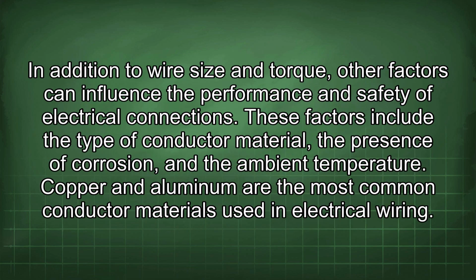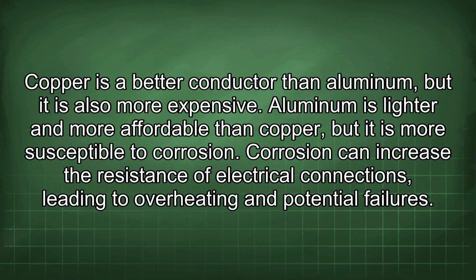In addition to wire size and torque, other factors can influence the performance and safety of electrical connections. These factors include the type of conductor material, the presence of corrosion, and the ambient temperature. Copper and aluminum are the most common conductor materials used in electrical wiring. Copper is a better conductor than aluminum, but it is also more expensive. Aluminum is lighter and more affordable than copper, but it is more susceptible to corrosion. Corrosion can increase the resistance of electrical connections, leading to overheating and potential failures.